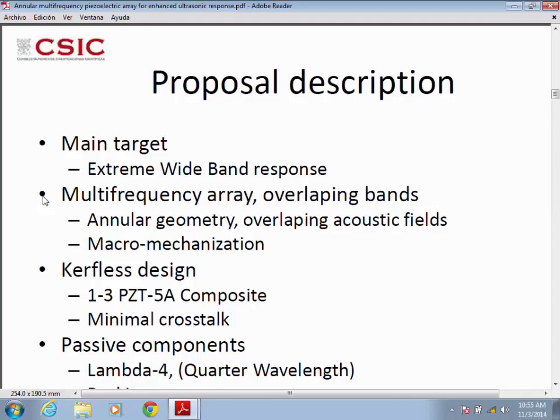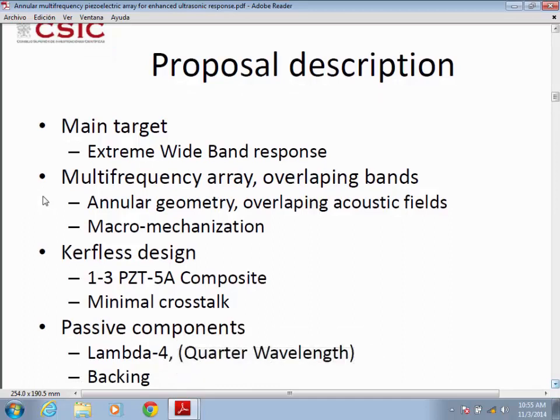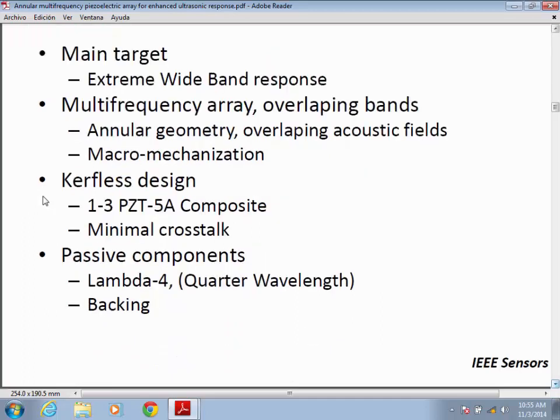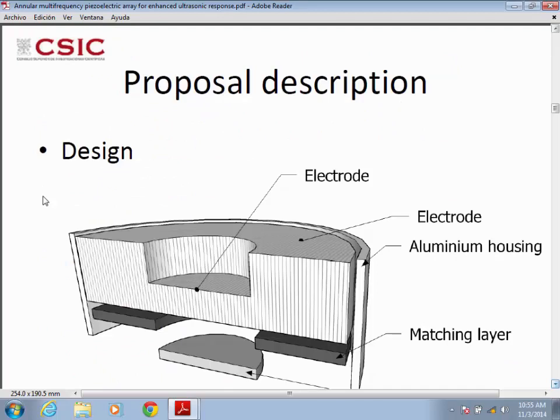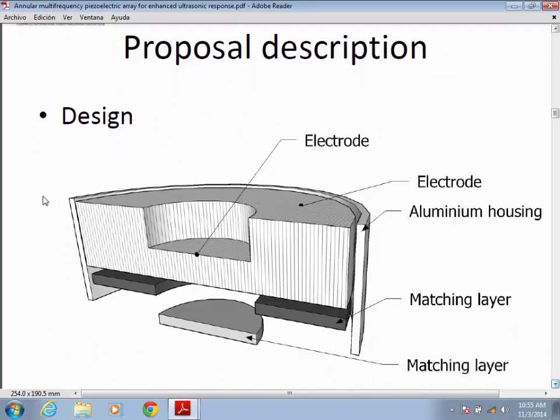In this case, we have a lambda fourth, quarter wavelength, matching layer at the front, and usually we add as well a backing layer in order to reduce the echoes that we don't want inside our signals. So this is the design. This is the ceramic, and we perform just a drill in the center. We encase it with an aluminum casing. We place electrodes on both surfaces, and we add a matching layer to reduce the mismatch with air or water in the case of this design.